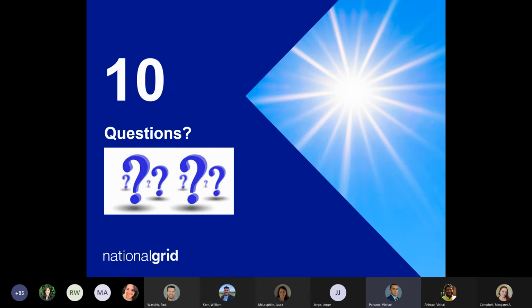Yeah, thanks, Will. So for the primary metering cluster, that is owned and maintained by National Grid, so that's a National Grid asset that cannot be customer owned. In terms of the least cost to serve analysis, that really is an examination of the company side equipment and what it costs to procure and install. Obviously, with a service of this nature, there's a customer side component too, so it does end up involving certain work that's not National Grid owned, it's customer owned. That would definitely be part of the discussion if the customer had a financial impact from going secondary or primary meter, and that would be factored into which way the service would go. But the main root of the analysis is based on the National Grid equipment.